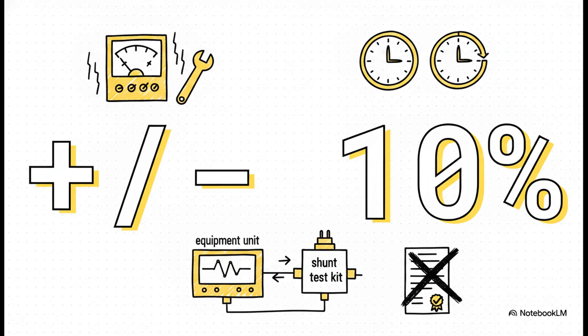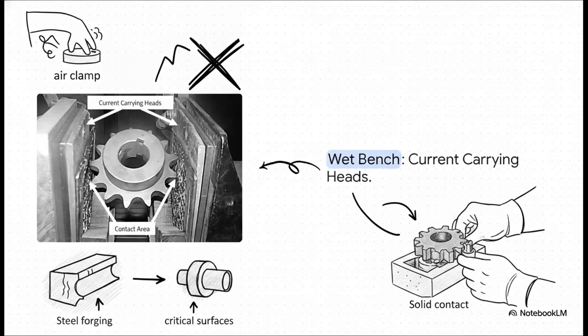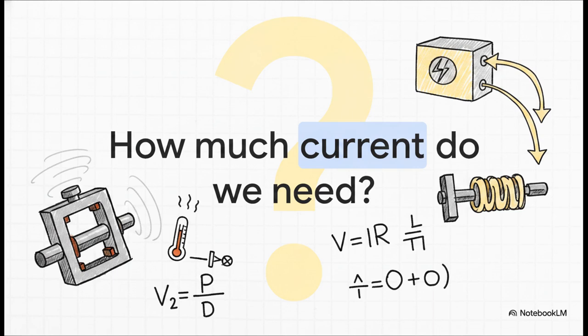You need to show you know that this check must be performed at 6-month intervals using a traceable calibrated shunt test kit connected in series with the output circuit. If your ammeter is off by more than that, the unit requires service, and your test results are completely invalid. Okay, so when you are interacting with the physical setup itself, you have to position your test specimen super carefully between the current carrying heads on the headstock and tailstock. You'll properly secure it using the air clamp to ensure really solid contact. This is absolutely crucial to prevent dangerous arcing that could ruin the part, especially on critical surfaces like the threads of a machined bolt.